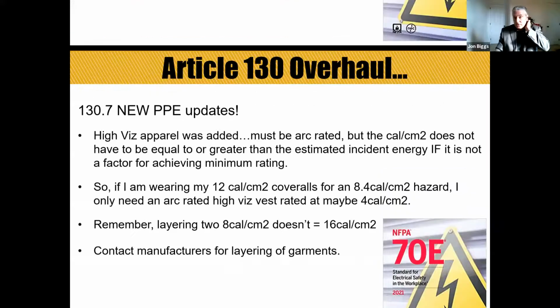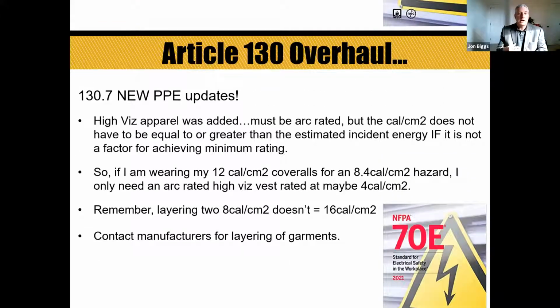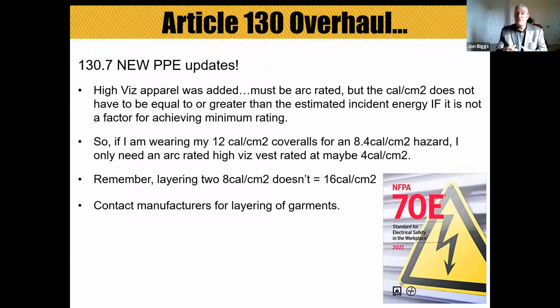Also, high-vis gear. So 130.7 gets into PPE updates. So high visibility gear like vests. You can get arc-rated vests. They absolutely exist. So this was added. But what I want you to note here is the calorie per centimeter squared rating on the high visibility vests does not have to be equal to or greater than the estimated incident energy of our equipment if it is not the primary factor for achieving minimum rating.